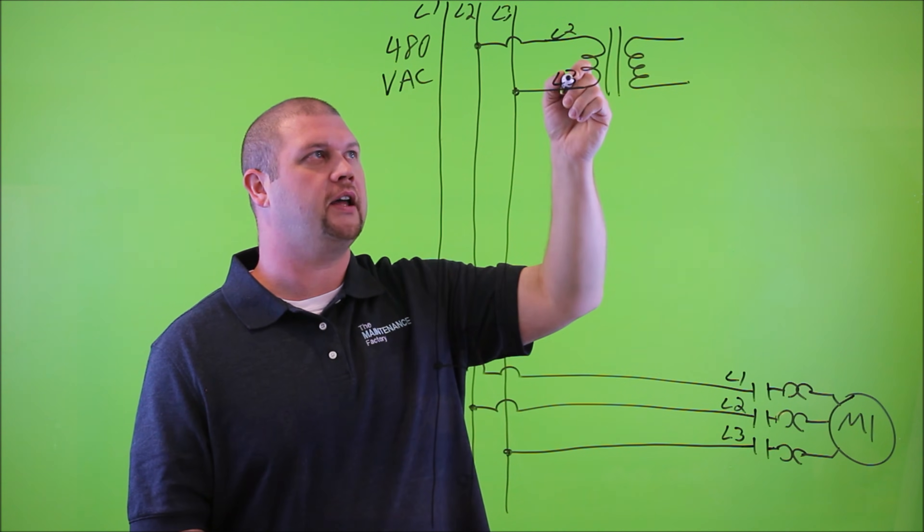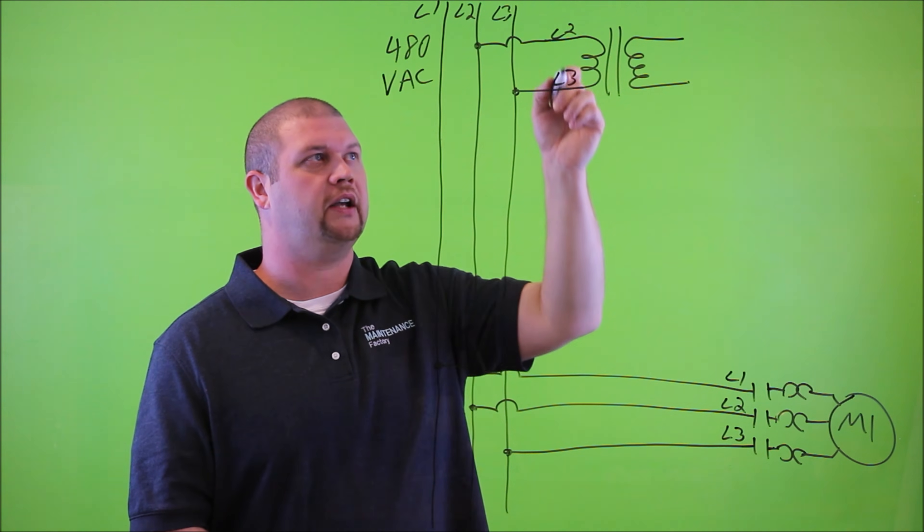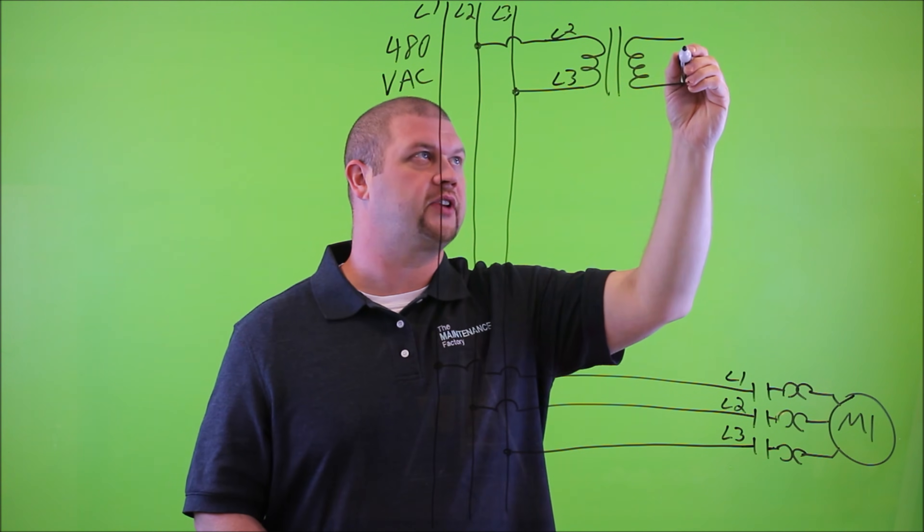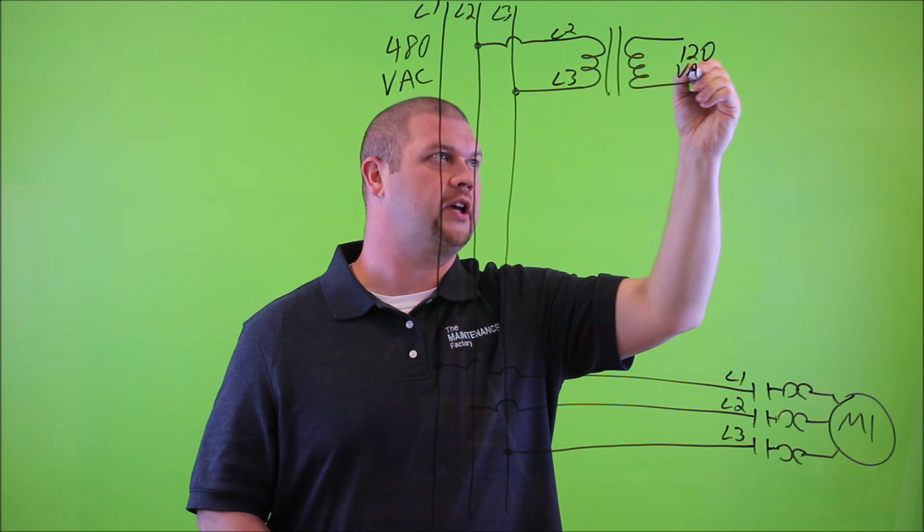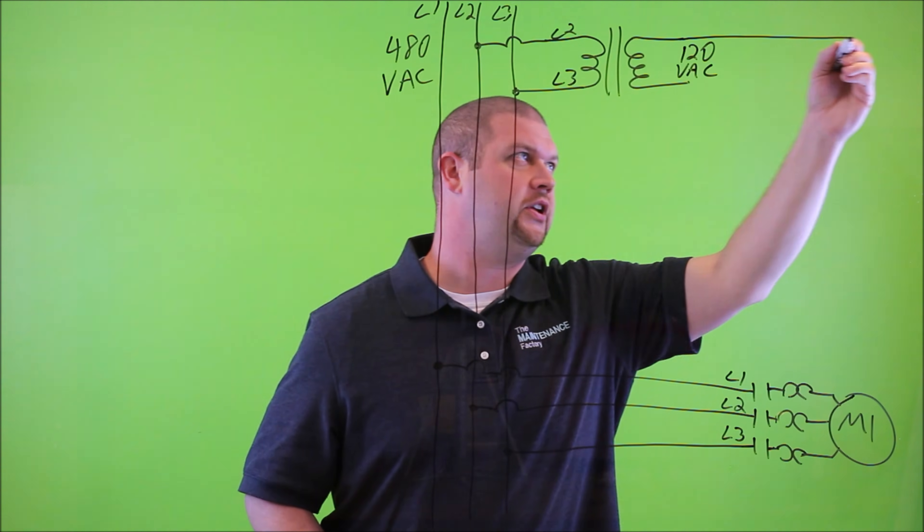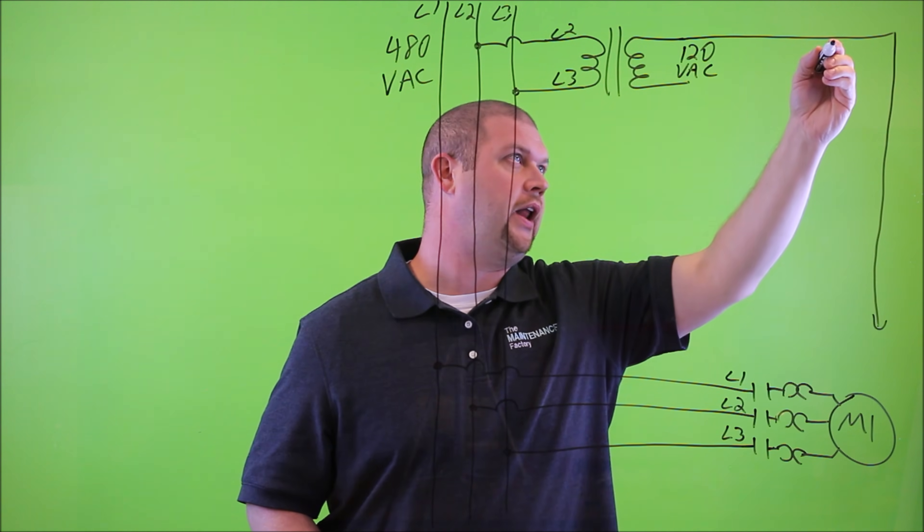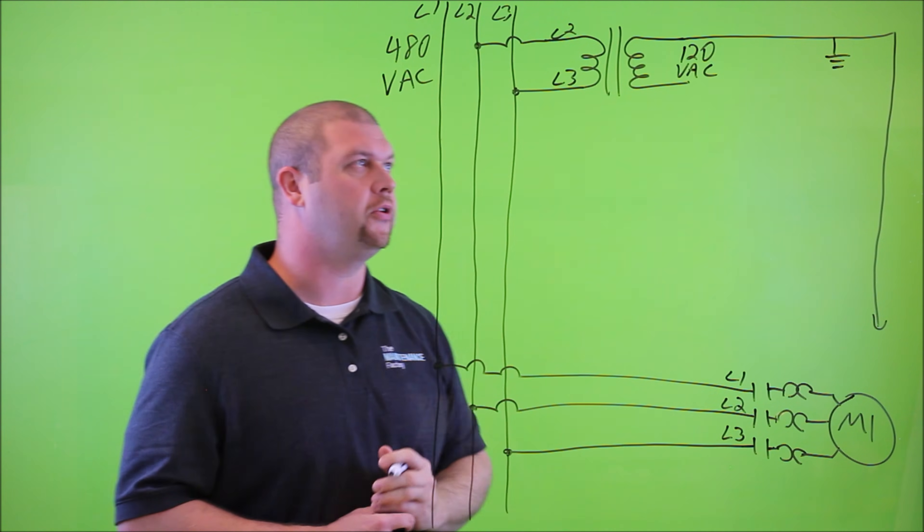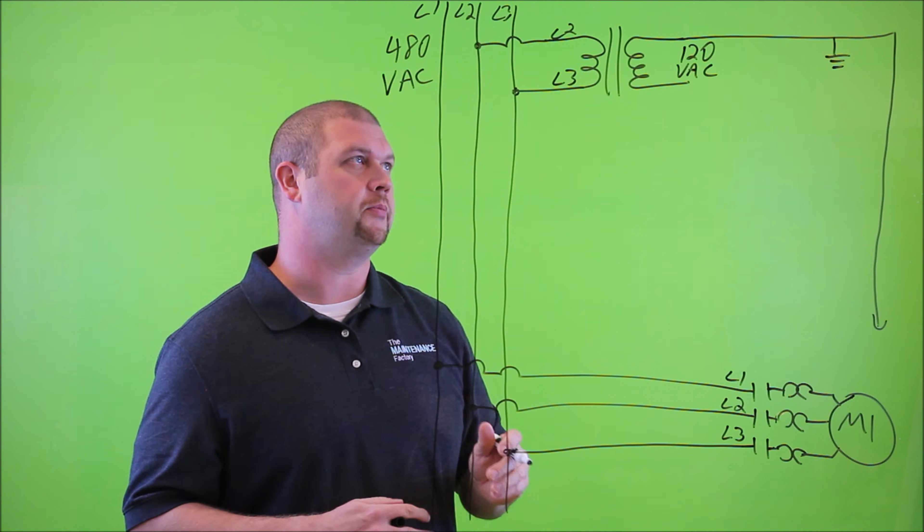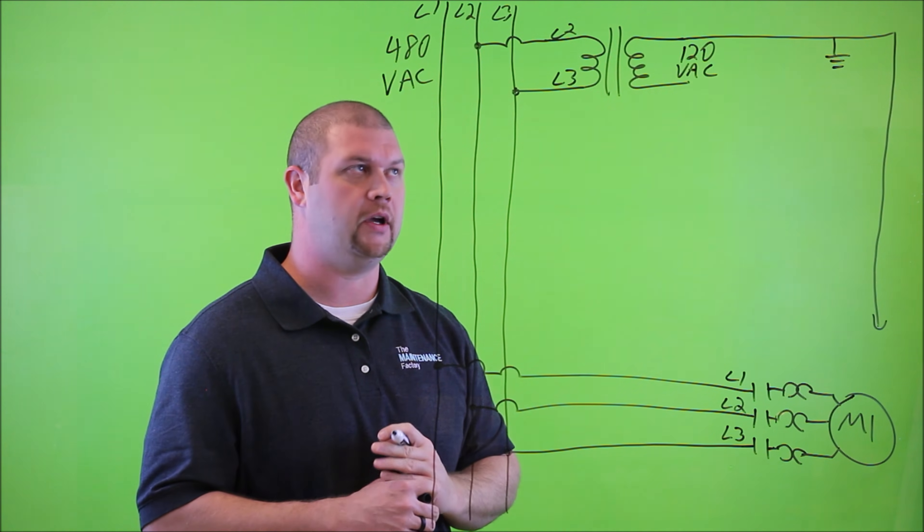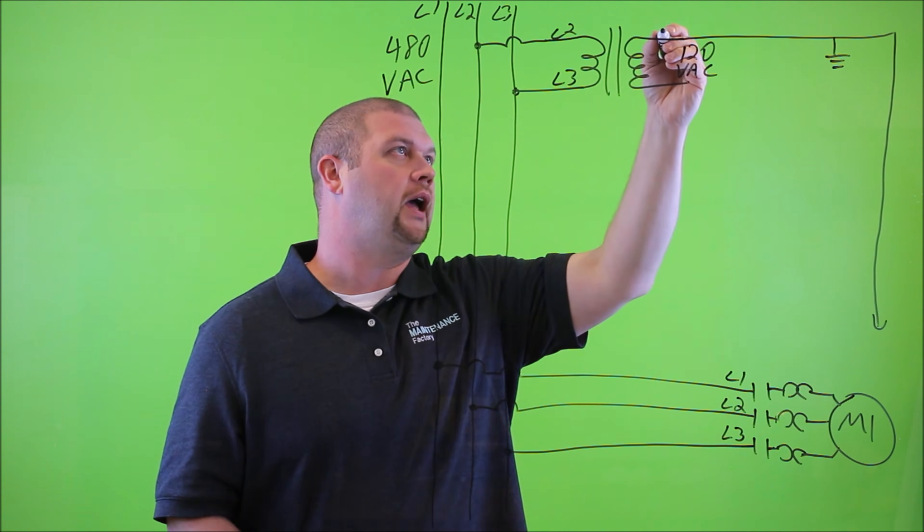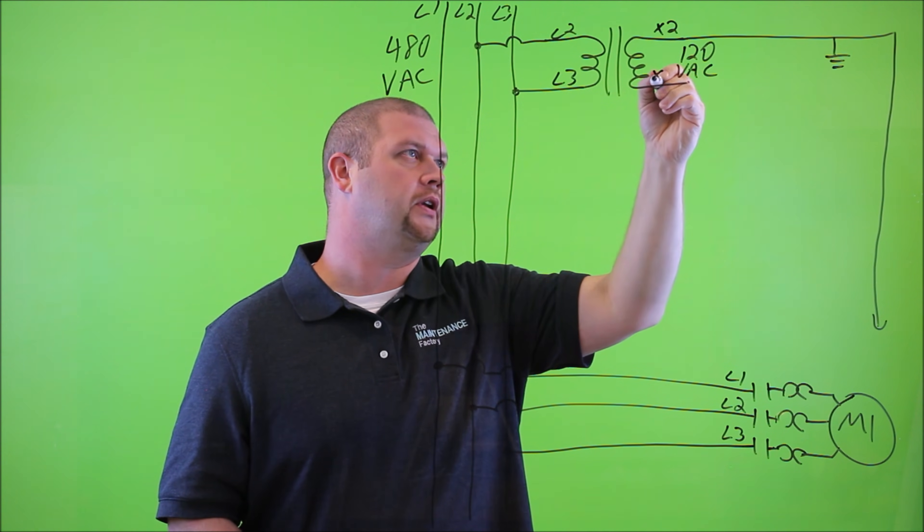So let's continue on by drawing a control transformer. And we're going to connect it to L2 and L3. On the line side, or the primary side of this transformer, it's connected to L2 and L3, which will be 480 volts AC. On the secondary side, we're going to say that steps down to 120 volts AC, which is just a little bit more user-friendly. And one side of this transformer is normally going to be grounded to the chassis or the housing of the equipment or motor starter bucket. And let's just name it X2 and X1.